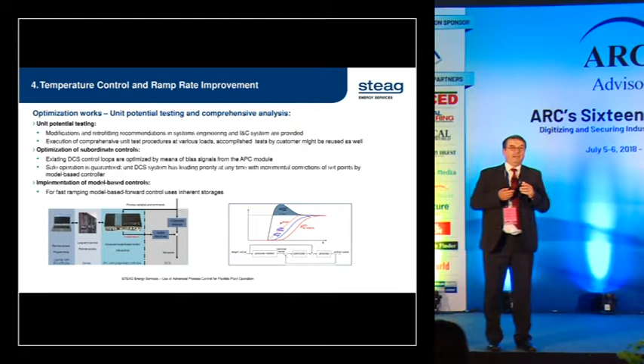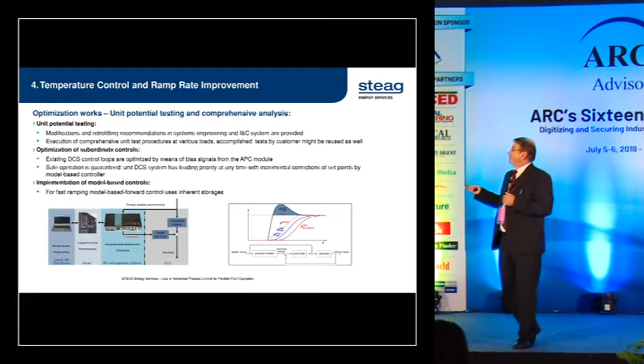An interesting fact, when I talk about this device and this approach, is that the theoretical base for this was developed 30 years ago. So pretty long ago, we developed the model which can calculate temperature differences based only on the rate of one temperature. But we used this model practically only for monitoring. Now, because of the flexibilization, there's a demand for very fast and effective control of the units. And there's now a new field for applying this model and this software for improving flexible operation of the plant.